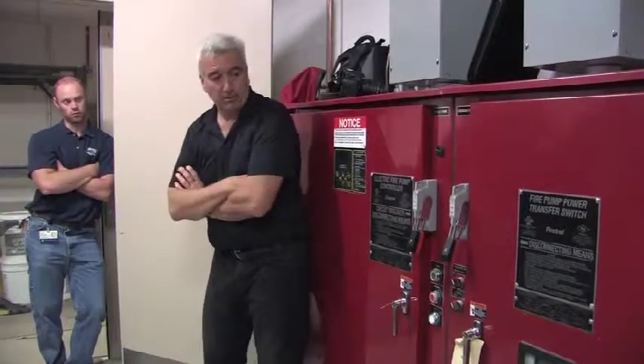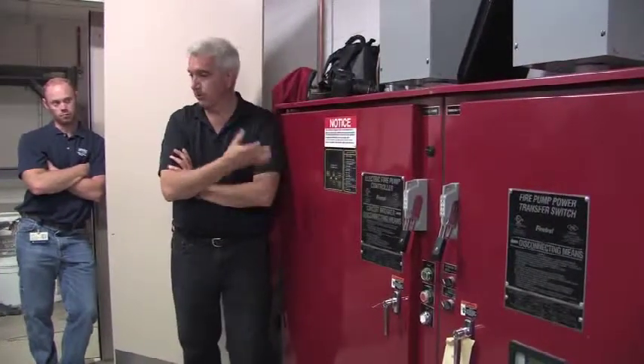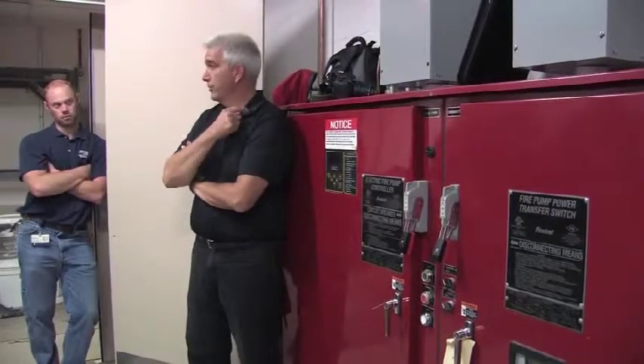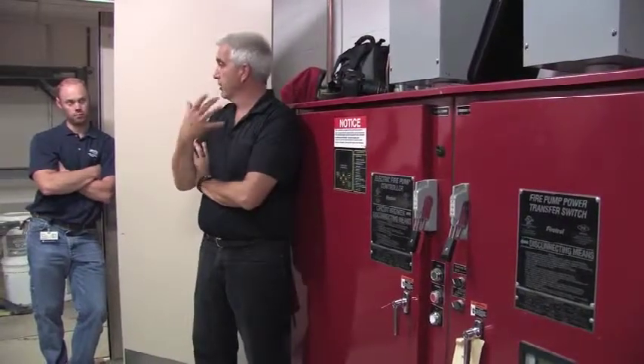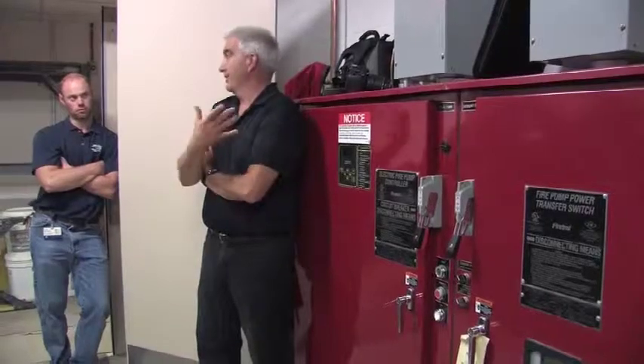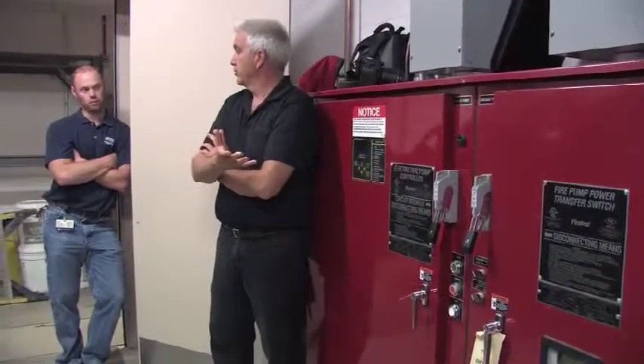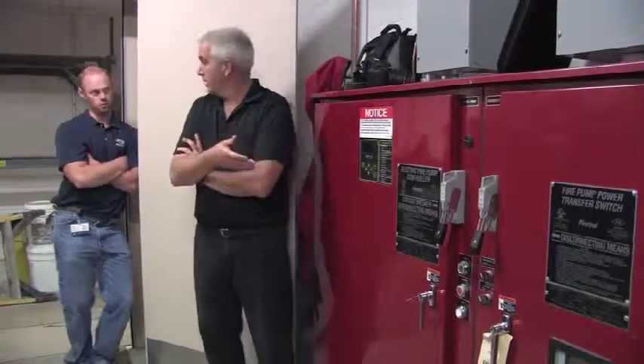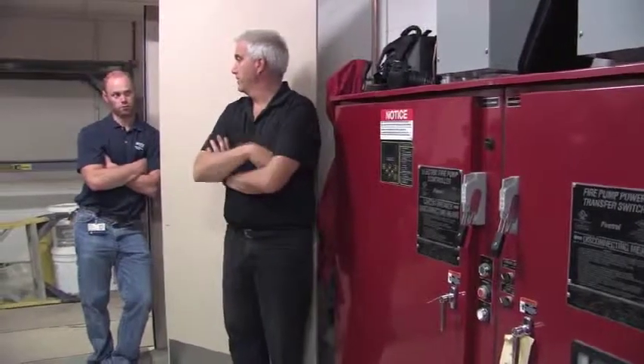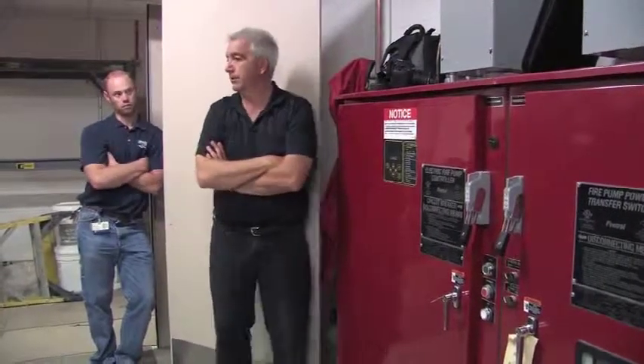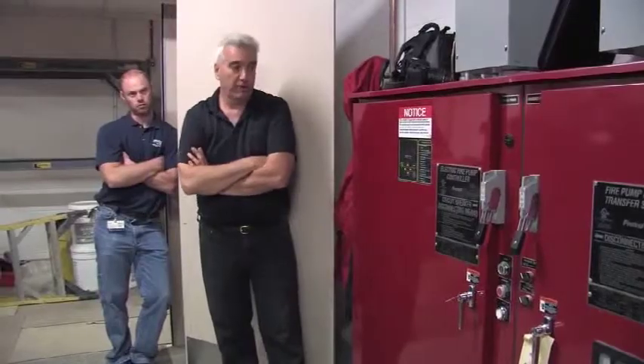What we do is we come in and we put it through all the normal start modes of operation. We do a generator test. We don't do any flowing, naturally. We just go through like doing your weekly test, but we take it to a whole different degree. And we give you a laminated check sheet. It really goes a lot further than what they recommend in the guidelines. But we do offer it.